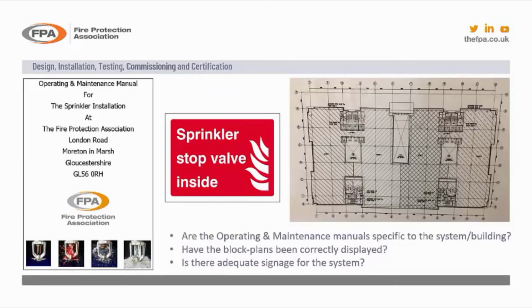Also at this stage, it would be required to be issued the system-specific operation and maintenance manual. Most companies have a generic one. This generic manual then needs to be site specific for the risk and the building and the components that are used in that building. The system, how it operates, what it's intended to do, what the monitoring of it is, what the off-site monitoring is, who's involved in the system. These are things that must be captured in the operating and maintenance manual.